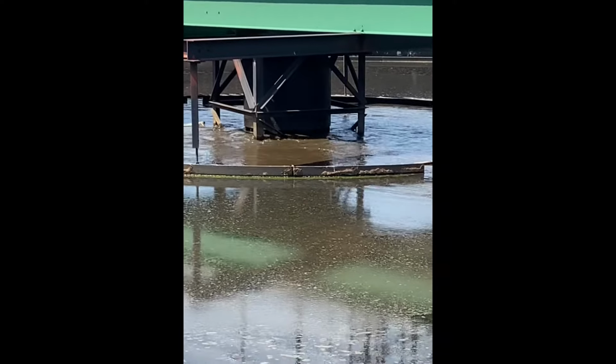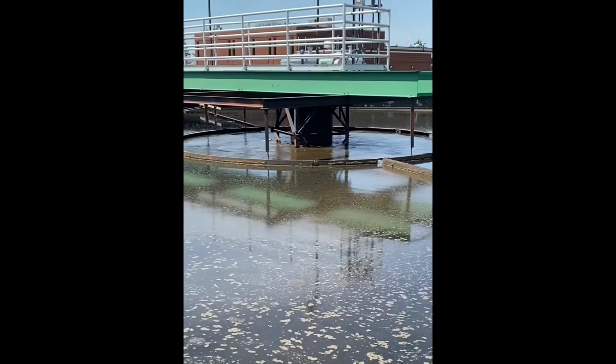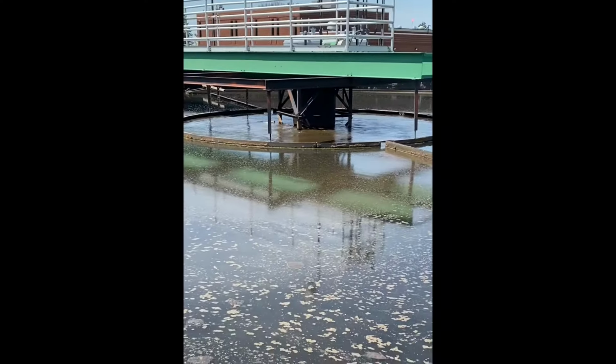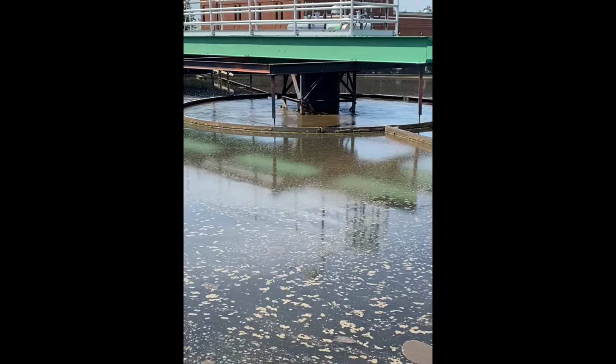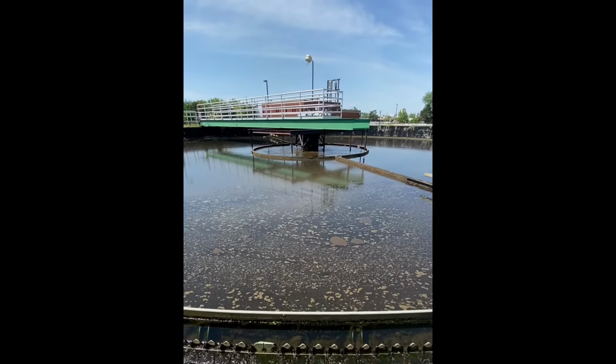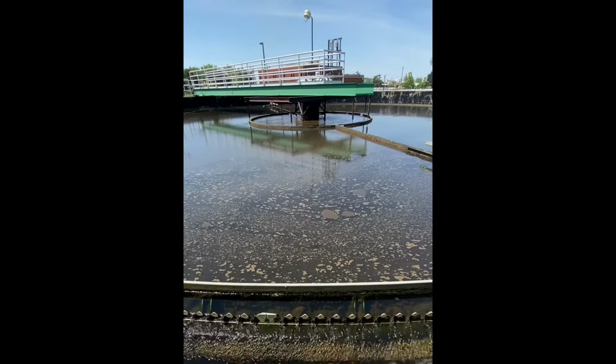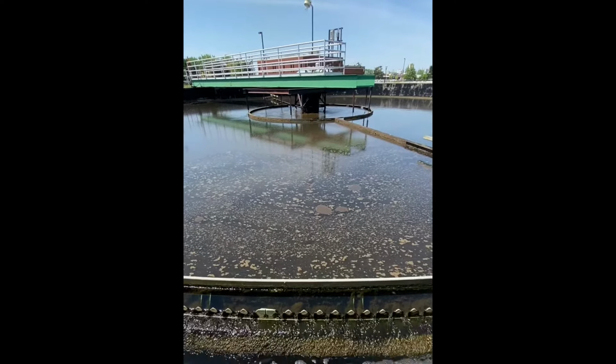This is the influent to this clarifier. I don't know if you can see, but that is the brown water, the mixed liquor directly from the aeration basin. They come into there. That inner ring is a baffled skirt down about 6 foot, so the water has time to settle out. This is about a 500,000 gallon clarifier, so it has detention time for the solids to settle down to the bottom.